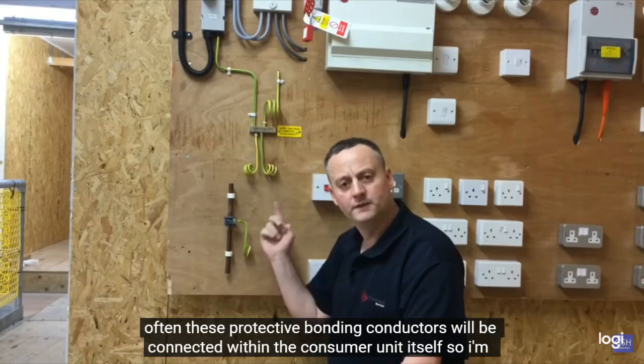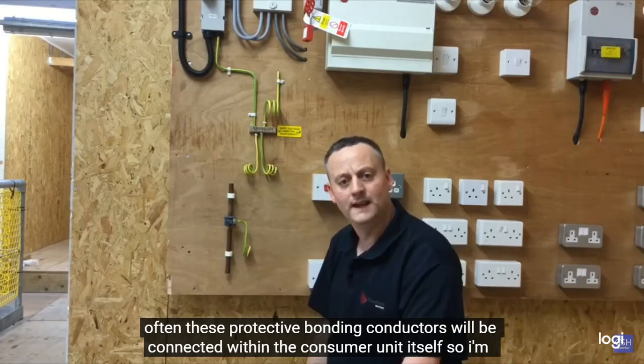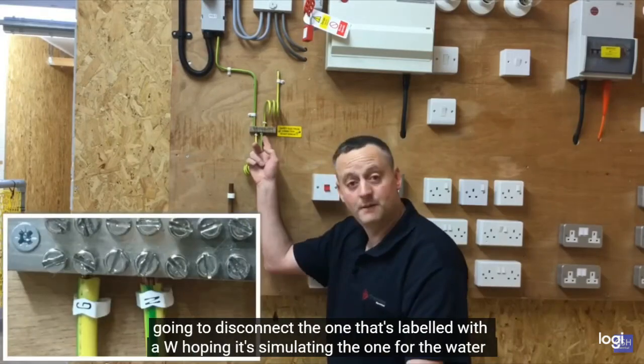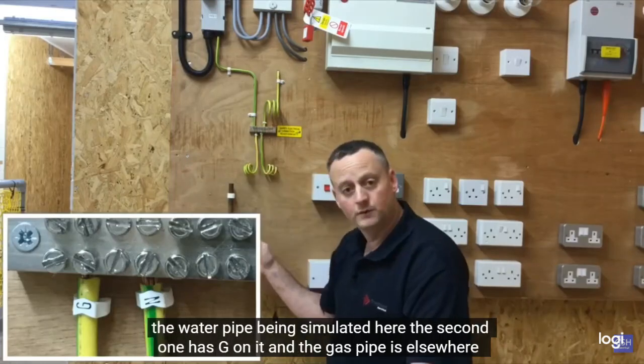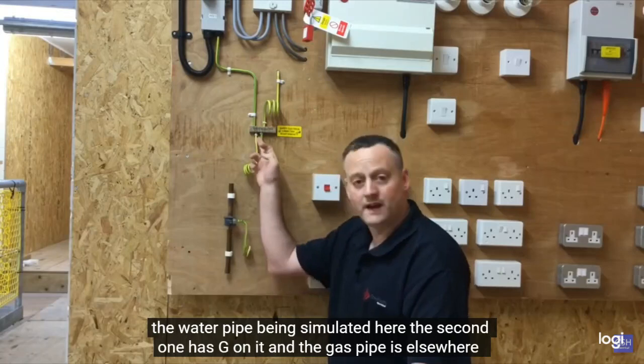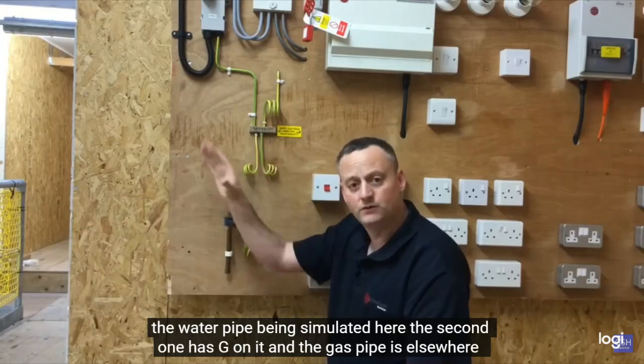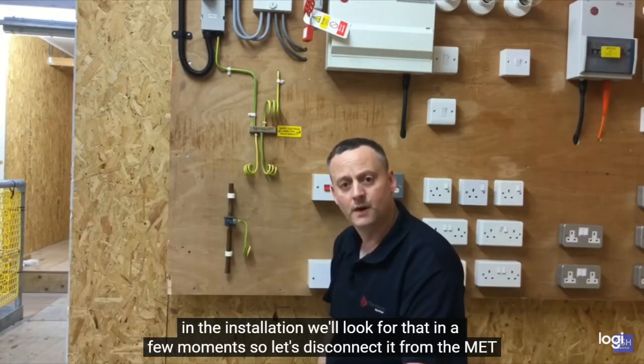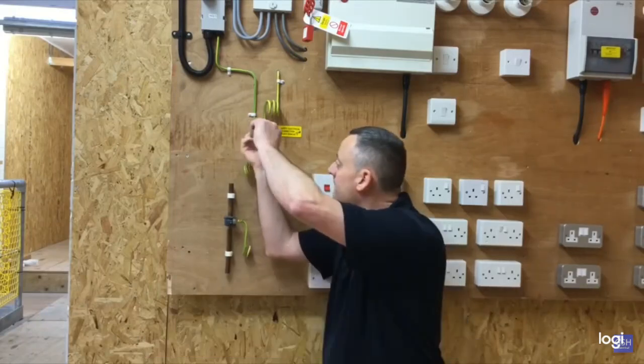Remember, often these protective bonding conductors will be connected within the consumer unit itself. So I'm disconnecting the one that's labelled with a W, simulating the one for the water pipe. The second one has G on it, and the gas pipe is elsewhere in the installation. We'll look for that in a few moments. So let's disconnect it from the MET.